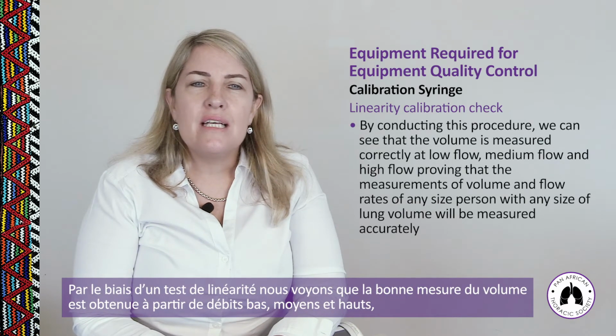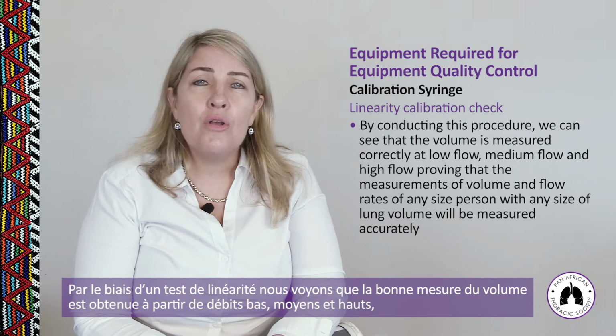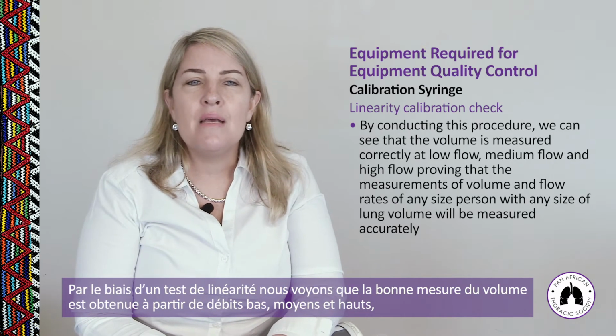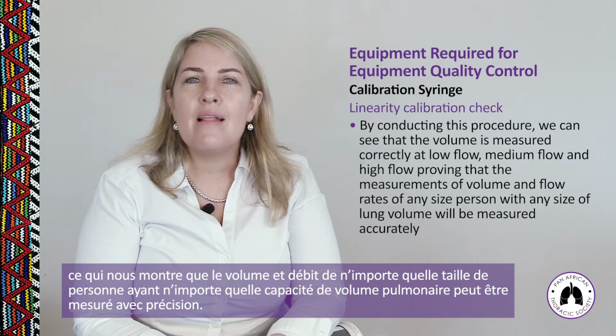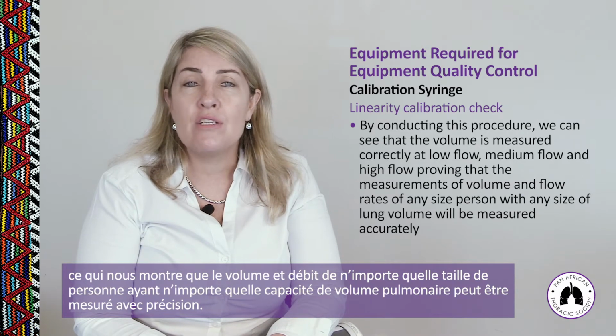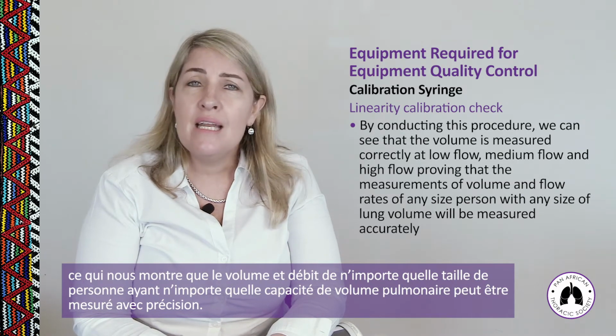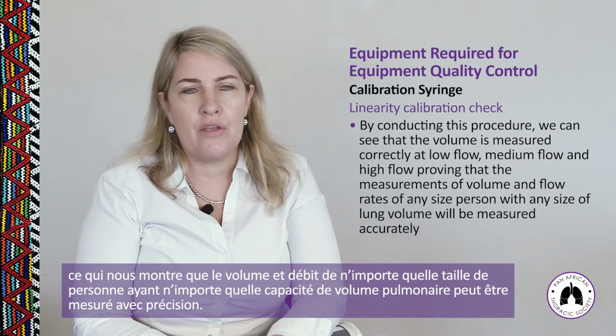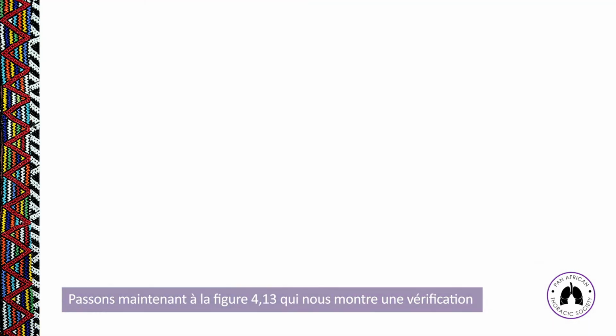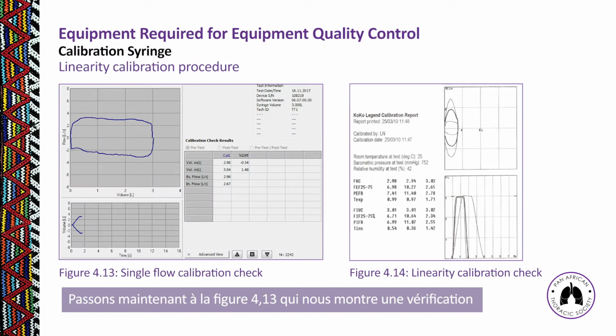By doing a linearity calibration check, we can see that the volume is measured correctly at low, medium, and high flow rates, proving that the measurements of volume and flow rates of any size person with any size of lung volume will be measured accurately. If you look at figure 4.13, this shows a single flow calibration check. What that means is that the syringe plunger was only moved once in and once out again, and we have looked at the volume measured at that moment.